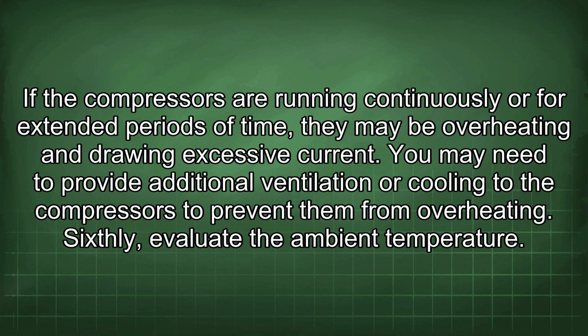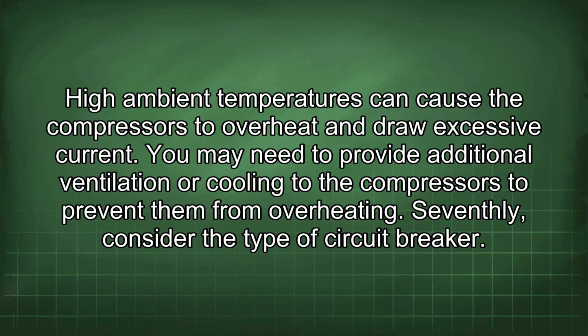Sixthly, evaluate the ambient temperature. High ambient temperatures can cause the compressors to overheat and draw excessive current. You may need to provide additional ventilation or cooling to the compressors to prevent them from overheating.